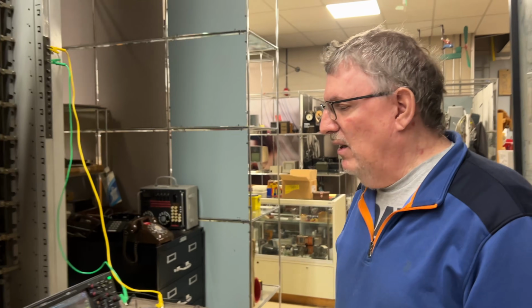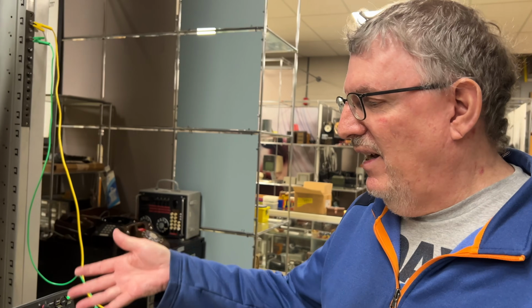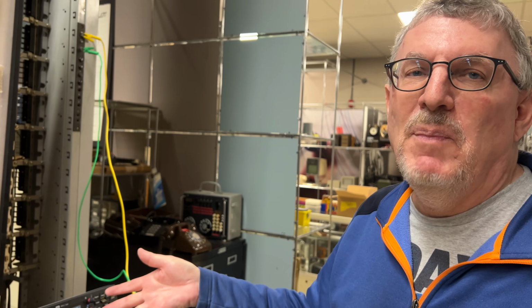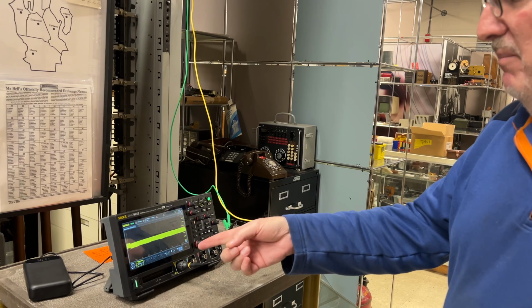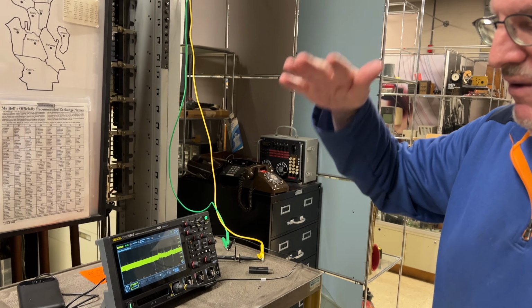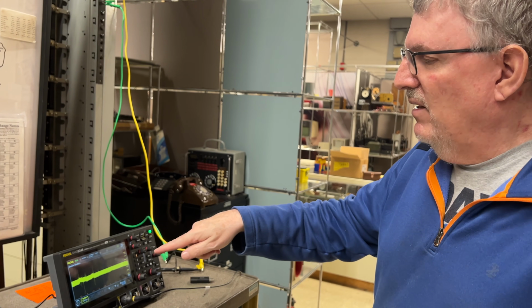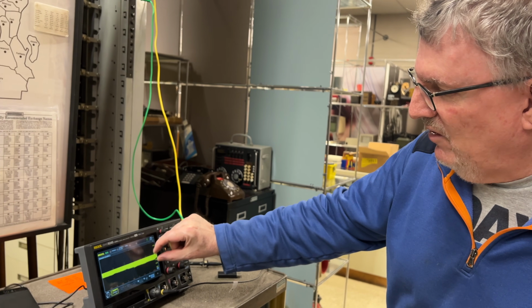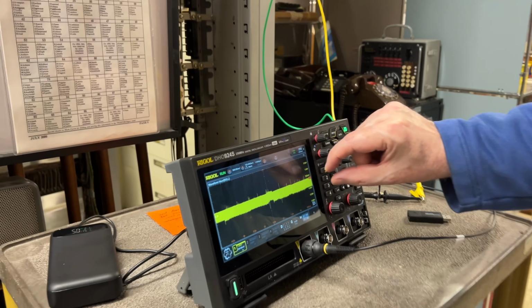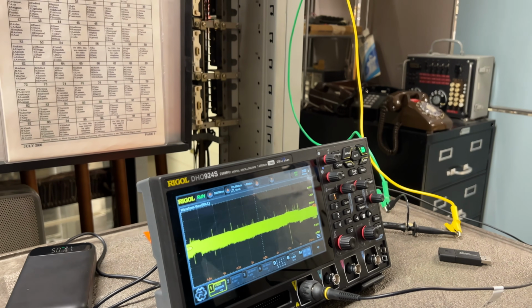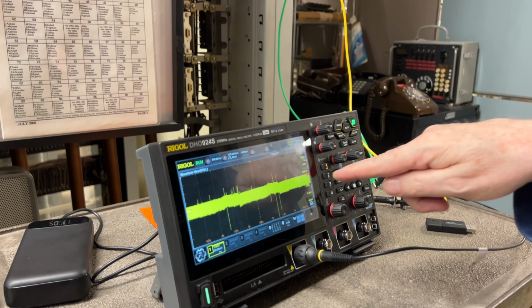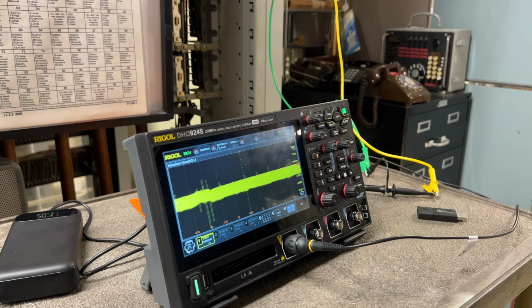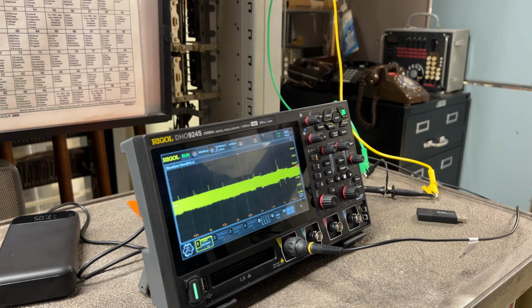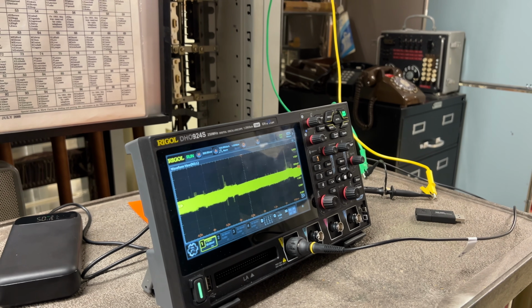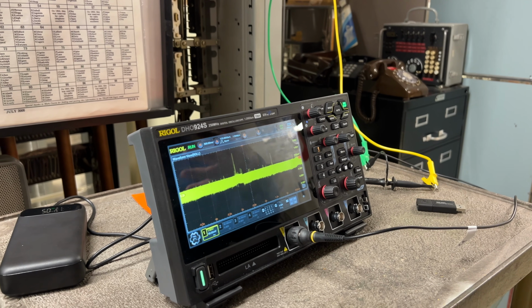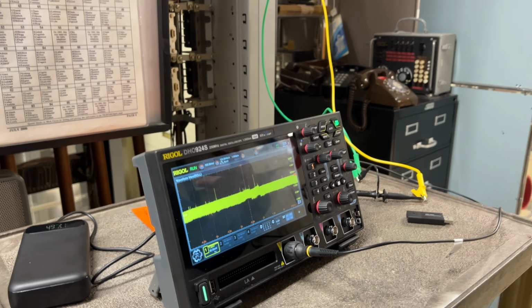This is just a look at the unfiltered battery voltage in the museum, AC coupled, so we've taken out the 48 volt baseline, and you can see there is this constant noise, which is just about 1 volt - that's just what the museum does. It's a combination of what's going on here in our part of the museum and what's going on in the Lumen part of it, because they're using power from that same source as well.